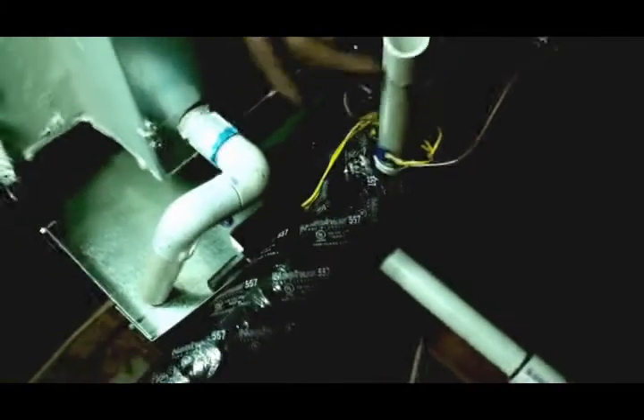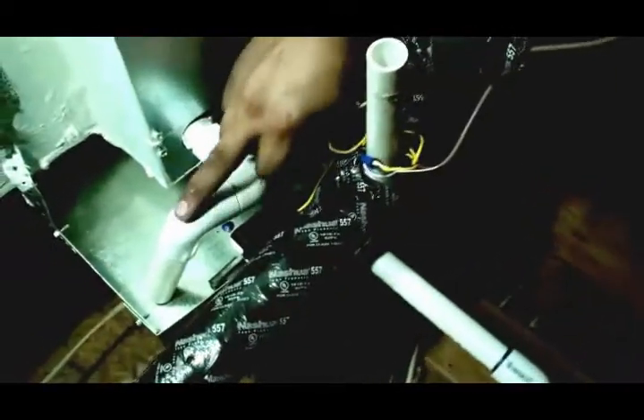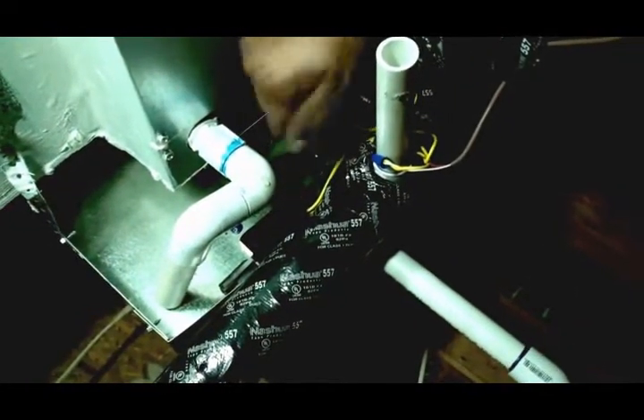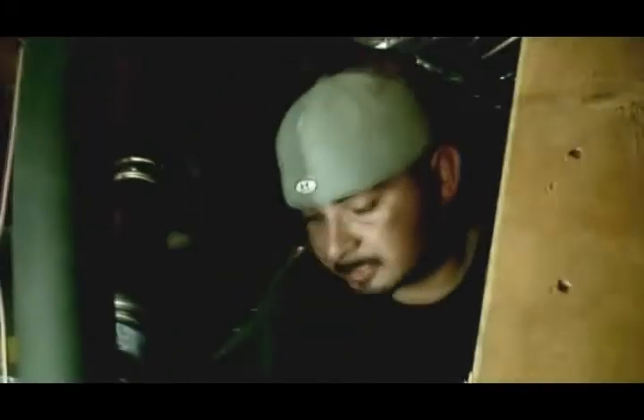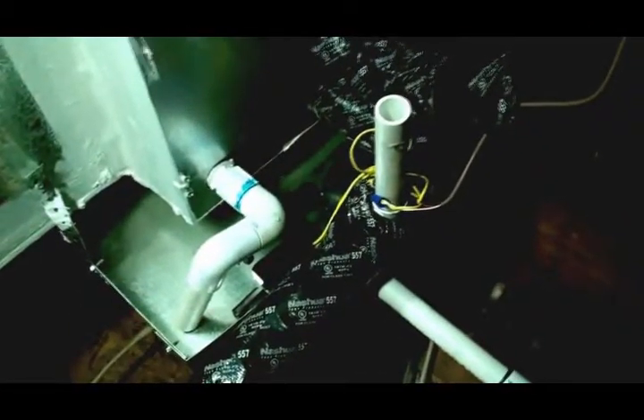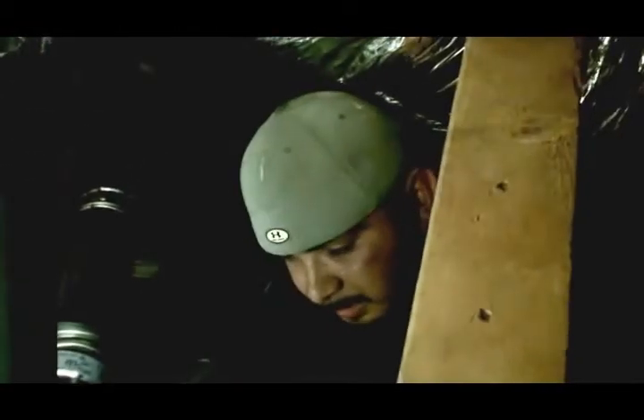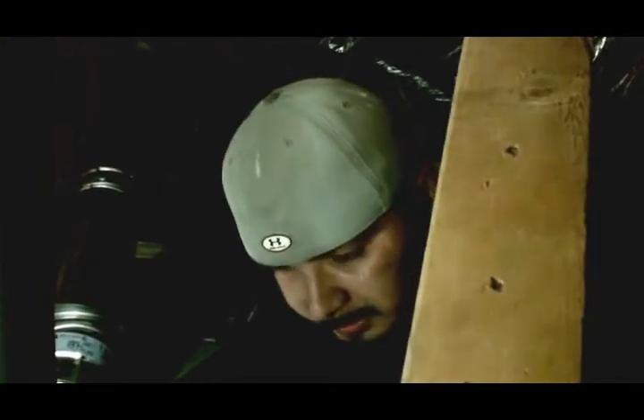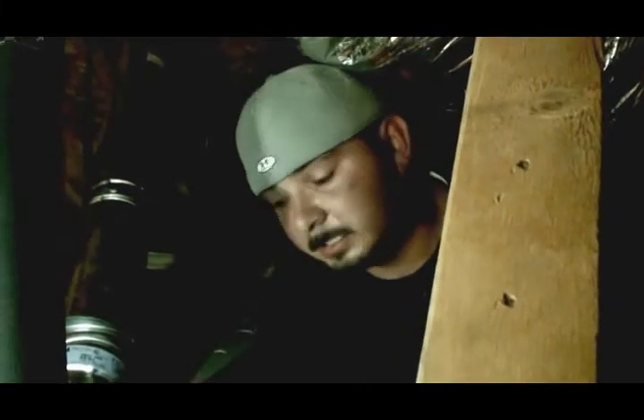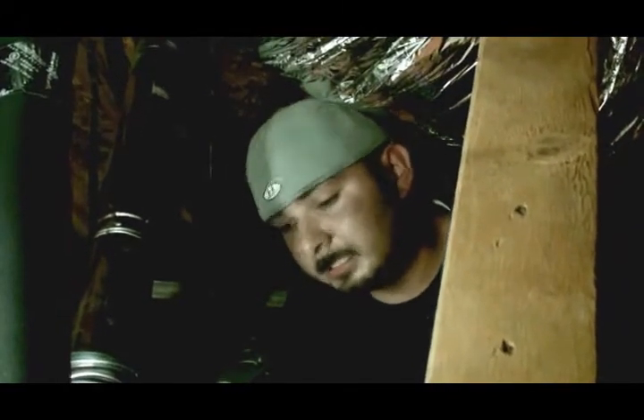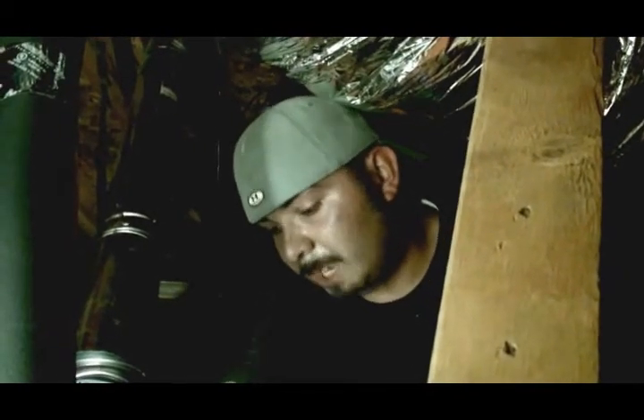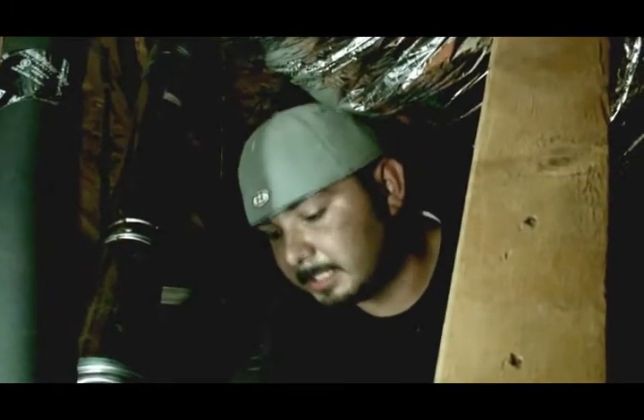Now, another added feature that we do to these systems is we add this float switch, which is a safety float switch, where if this main drain ever does clog up, this secondary will overflow, and it won't let it get over 1 inch of water in this drain pan until it finally cuts off the system altogether, to allow that secondary drain to drain out and to prevent any kind of water damage. So again, that's why we always let the homeowner know this secondary drain, we let them know exactly where it pipes out outside. So if there's any water flowing through it or coming out outside, then you have a problem with your main drain, and we'll have to come up here, check it out, and blow it out, whatever needs to be done. But basically, that's the whole gist of the system.